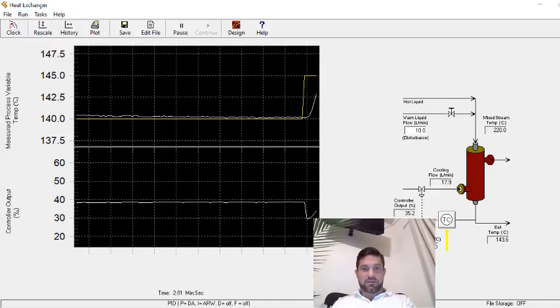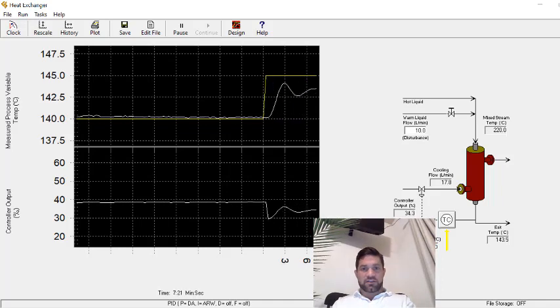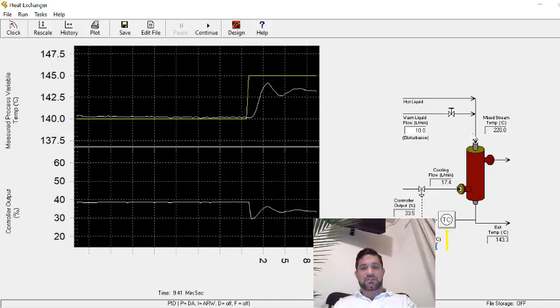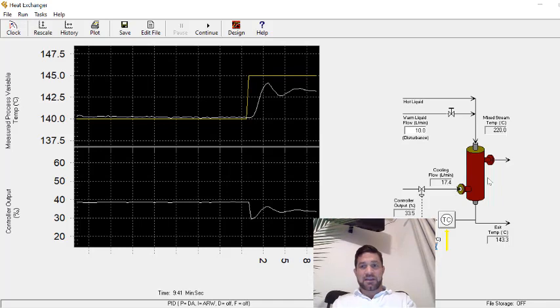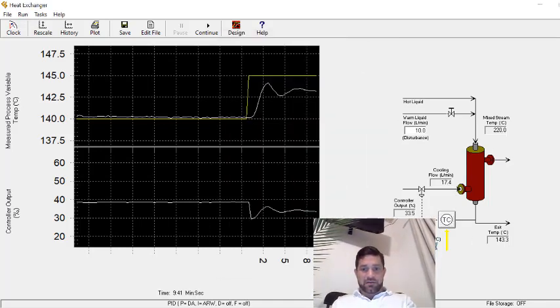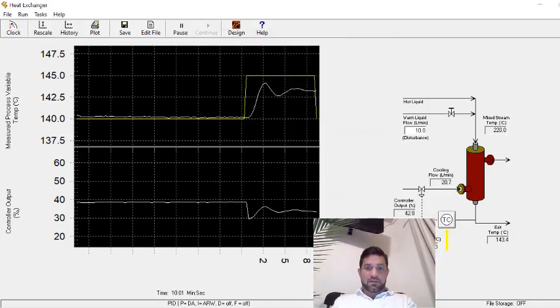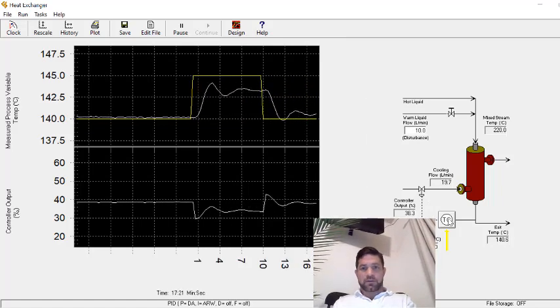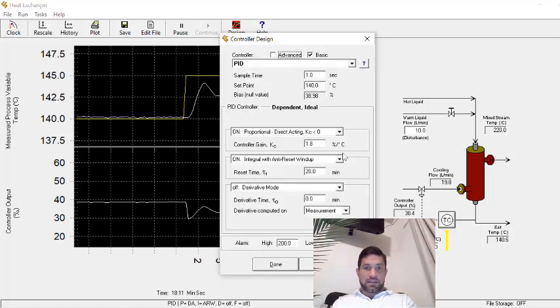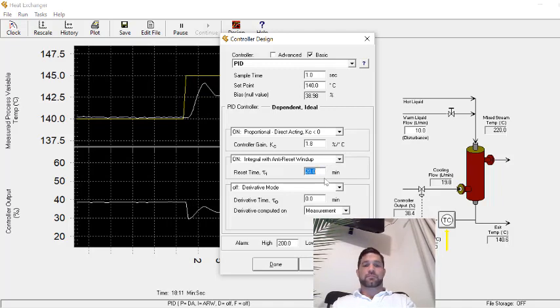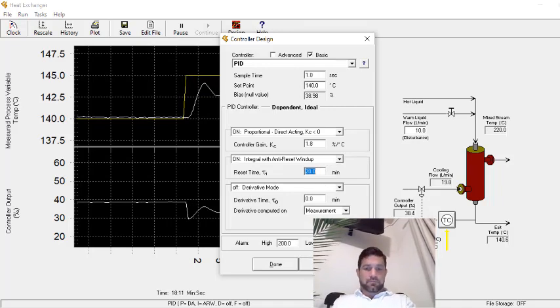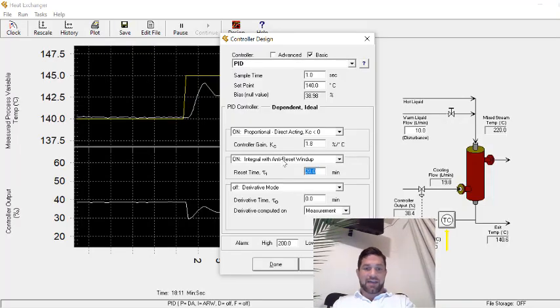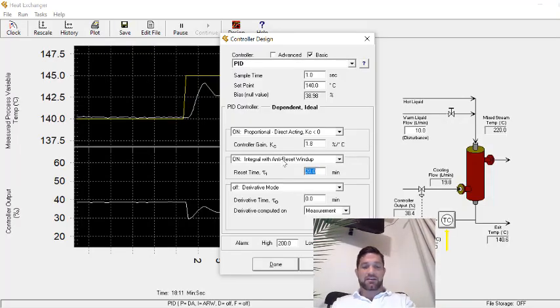Now let's see how this works with the step change to 145. We see first peak to valley. Now we're looking a little bit closer to 16%. It might be a bit high. I want to come back down to my starting point. So what I want to do is cut τI in half and try again, so 10. Cut it in half.